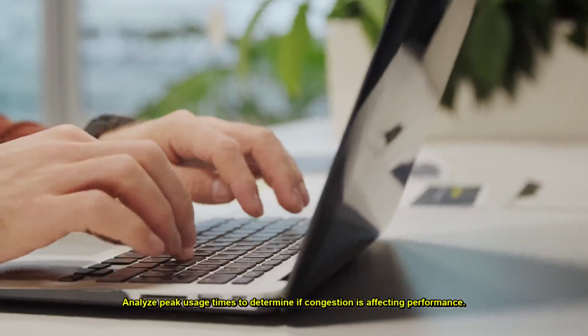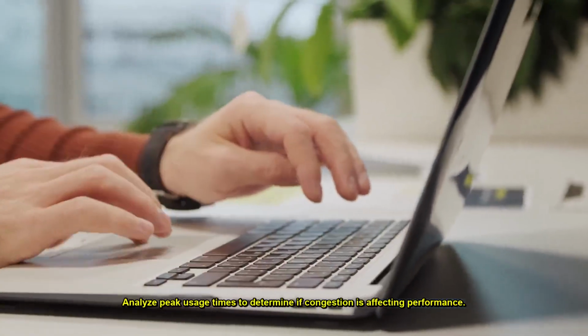Monitor the charging session history for patterns related to speed drops. Analyze peak usage times to determine if congestion is affecting performance. Consider adjusting the load balancing settings if multiple stations are connected to the same circuit. Test the charging station using different vehicles to identify if the issue is vehicle specific.